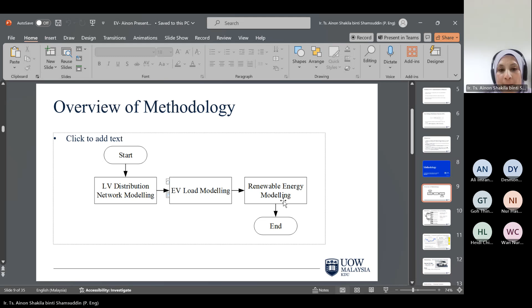The low voltage distribution network model used in this project is an actual distribution network located in Port Dickson, Malaysia. So the incoming voltage level from the transmission system is 11 kilovolt, and the voltage supplied to the consumer is 415 volts, three phase. This system uses transformers which step down the voltage from 11 kilovolt to 415 volts. There are two transformers in the system, rated 500 kVA and 750 kVA respectively, and the connection is delta-Y.